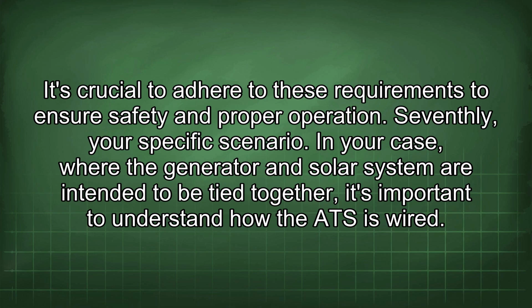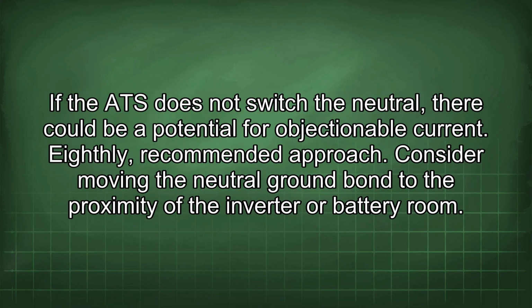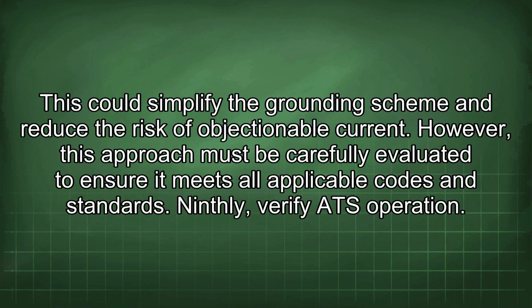Seventhly, your specific scenario. In your case, where the generator and solar system are intended to be tied together, it's important to understand how the ATS is wired. If the ATS does not switch the neutral, there could be a potential for objectionable current. Eighthly, recommended approach. Consider moving the neutral ground bond to the proximity of the inverter or battery room. This could simplify the grounding scheme and reduce the risk of objectionable current.